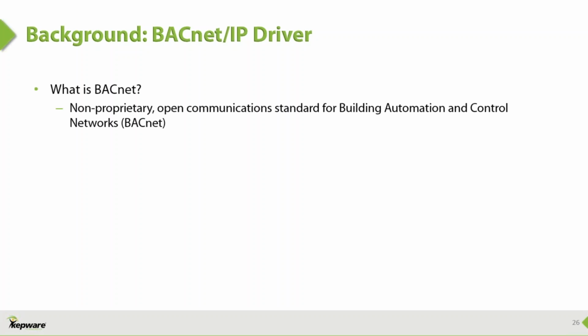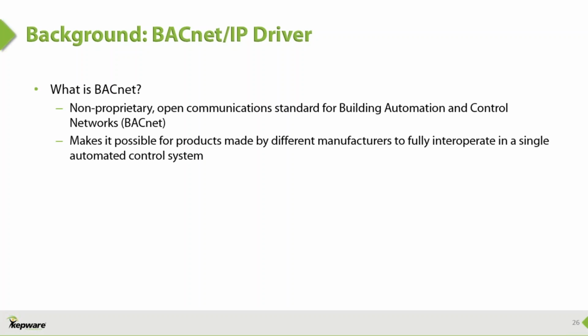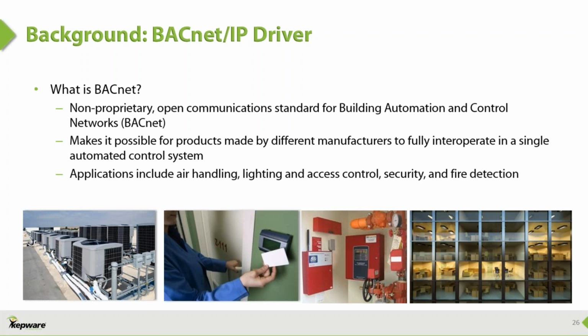BACnet is essentially a communications protocol for building automation and control networks. It's a completely non-proprietary, open standard developed specifically for the control and monitoring of building automation controllers and devices—think thermostats, sensors, chillers, heating elements, and similar items that are all around us. The standard is about interoperability among vendors, enabling quick data exchange between hardware and software products such as building automation controllers, gateway devices, routers, operator workstations, and diagnostic tools. Typical building automation applications include heating, ventilation, and air conditioning control, lighting, physical access control, security, waste management, and fire detection.